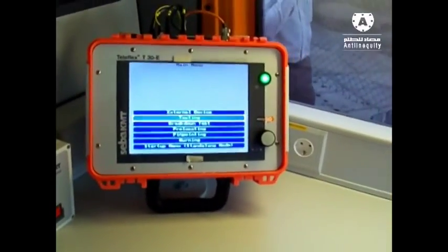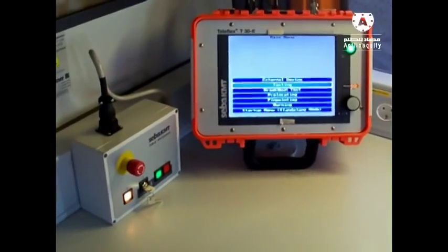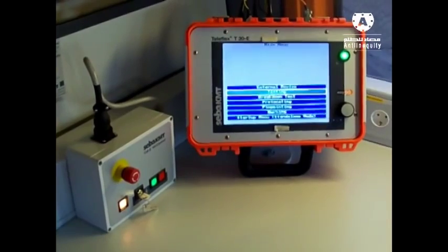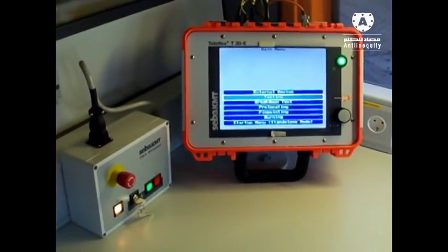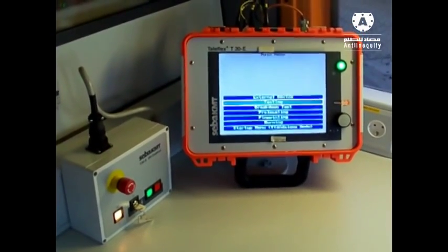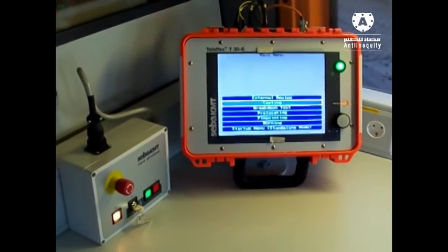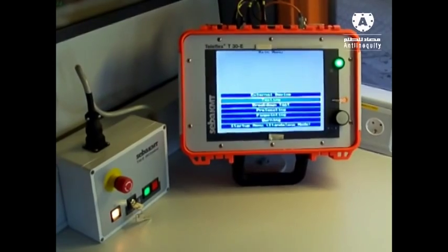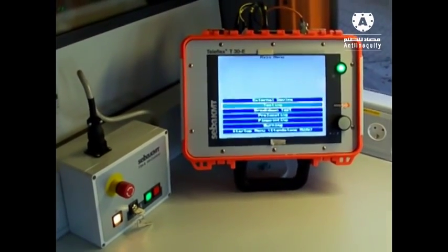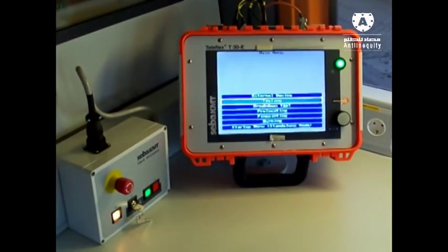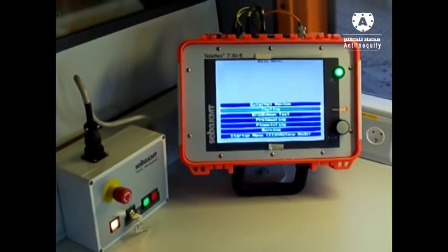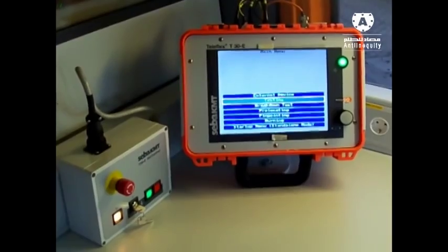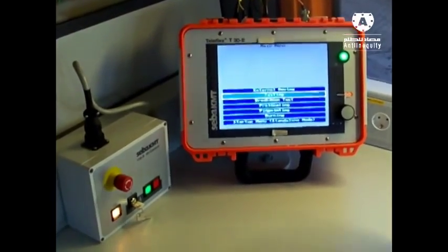After I get an idea about the failure by testing, I can now have a look inside the faulty cable with my TDR, because I want to see if it is a break on the way from the beginning to the far end, or what happens. And also I want to try to get the real velocity of our cable length to get the best results for the next step for arc reflection mode.